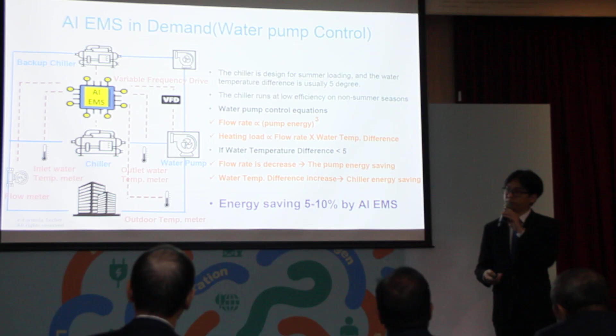method. Okay, the previous slide only shows the water pumping control, but indeed the whole chiller system also has a cooling pump, cooling tower, AHU, or even a room pump, or even you have more and more chiller systems. Okay, so all the equipment should be controlled and optimized at the same time. So we must use the AI fuzzy system to control all of them. And usually, in my experience, the total control will get about 15% energy saving. Okay, so this is the first example.